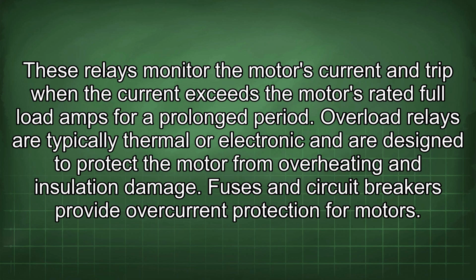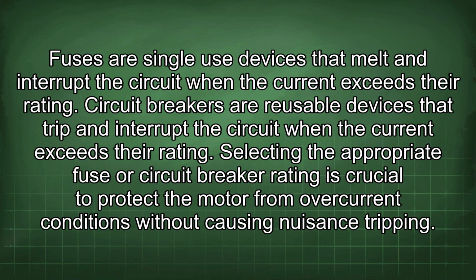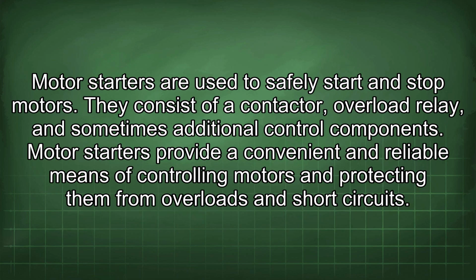Fuses and circuit breakers provide overcurrent protection for motors. Fuses are single-use devices that melt and interrupt the circuit when the current exceeds their rating. Circuit breakers are reusable devices that trip and interrupt the circuit when the current exceeds their rating. Selecting the appropriate fuse or circuit breaker rating is crucial to protect the motor from overcurrent conditions without causing nuisance tripping. Motor starters are used to safely start and stop motors. They consist of a contactor, overload relay, and sometimes additional control components. Motor starters provide a convenient and reliable means of controlling motors and protecting them from overloads and short circuits.